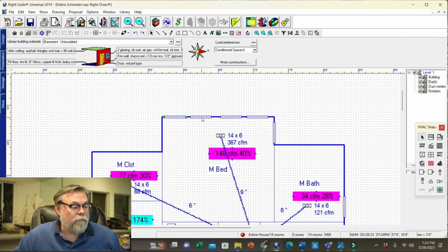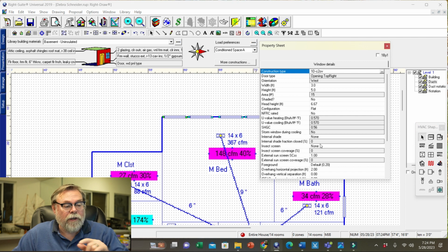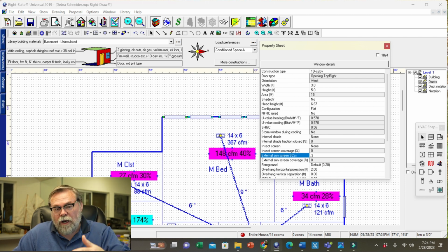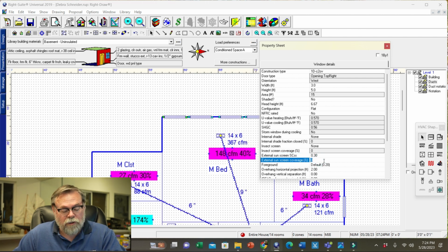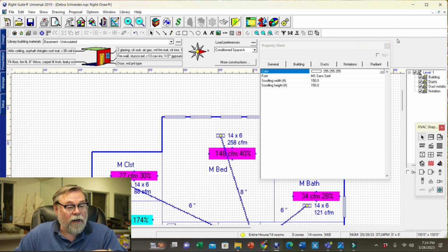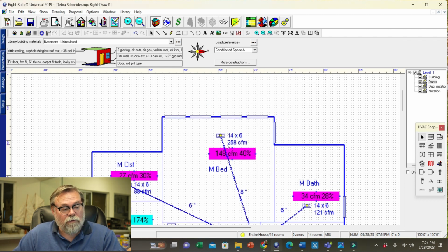Well, I got to click on all of them. Let me click on all of them real quick here. Boom. And then I'm going to put sunscreens. With sunscreens, we're going to be about 0.3 or 3.5, but typically that's how much shading it can get out of sunscreens. And then we're going to make them 100% on just those 4 windows and see what it changes. Well, suddenly we went down to 258 CFM just by doing those 4 windows, okay?